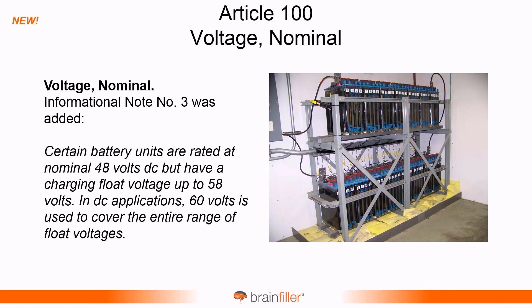For 'nominal voltage,' this change concerns DC voltage. Certain battery systems are rated 48 volts nominal but can have a float charge up to 58 volts. So in DC applications, 60 volts is used to cover the entire voltage range. A new informational note was added to address this.